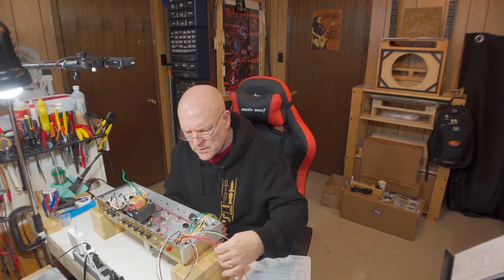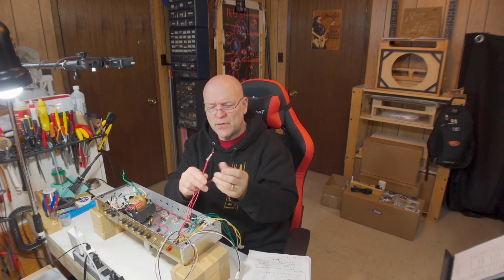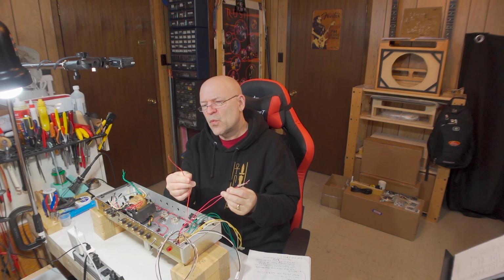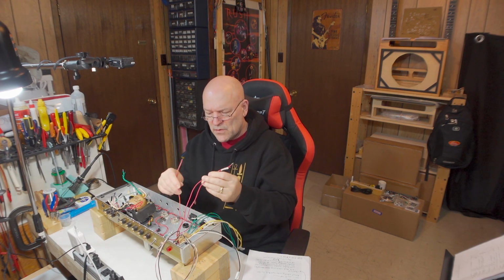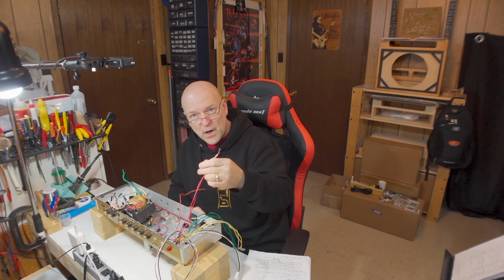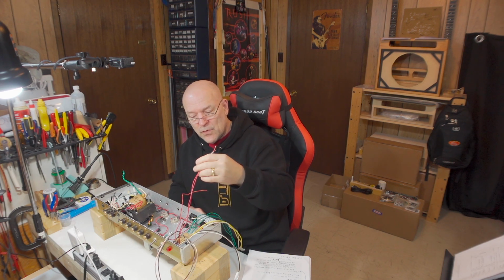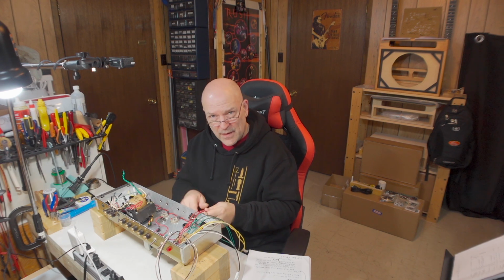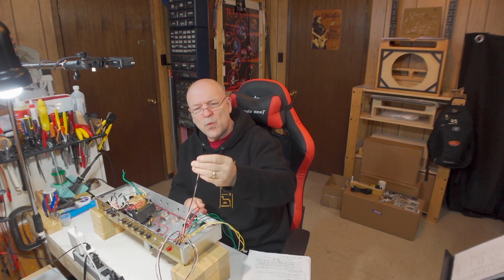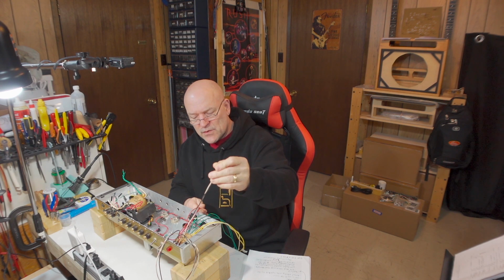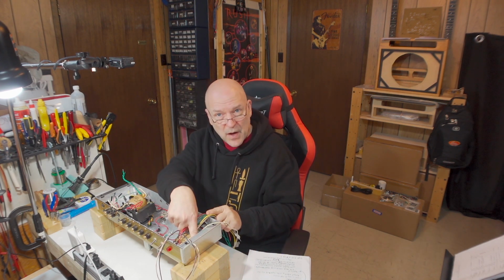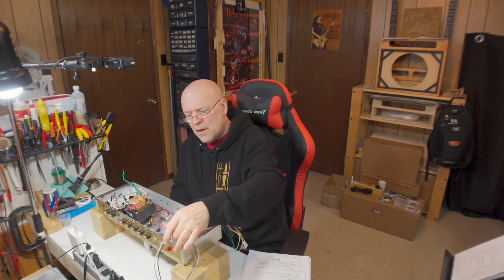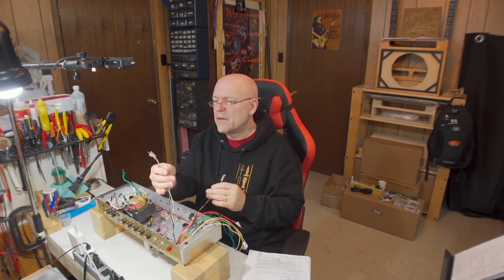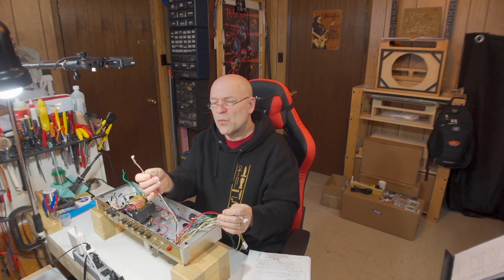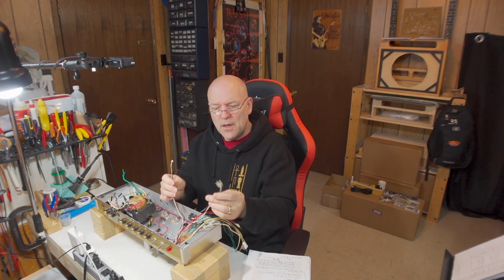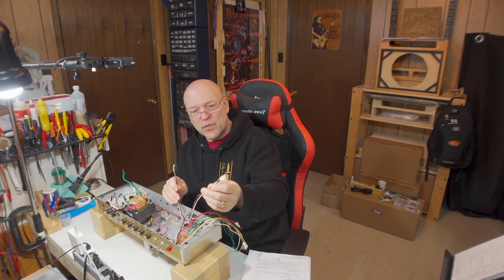Then I went over to the other side. For the high voltage windings, we have a red wire with a yellow stripe that goes to ground, and the two red wires are the high voltage supply, which twist together and connect as described before. The white wire and black wire twist together, solder together, and go to our common power point. Then there were two pairs: the white with the red stripe and black with the red stripe, and the white with the black stripe and black with the white stripe.